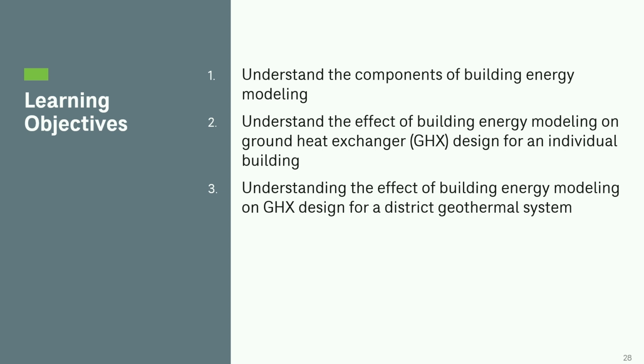I don't know if I would be the one to put that standard out there. I think that'll be a collective effort of how much drift we would allow. It's really driven by those entering water temperatures. If we exceed what we want for the equipment, that's when we would say this would be too much drift. Correct. So the question was, as long as you were within the minimum and maximum entering water temperature, it would be okay for that system. I think we have one over here and then one over there. Oh, never mind.